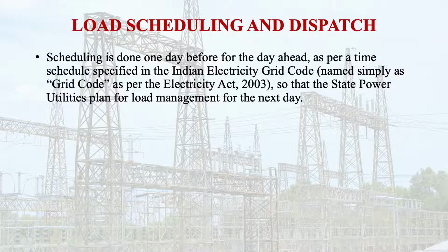Load schedules are prepared on a 15 minute basis. That means the load dispatch center prepares the schedule, or gets the schedule from the states or from the generating plants. It is scheduled on a 15 minute basis to see that the average generation of electrical energy over 15 minutes matches the load over those 15 minutes. The scheduling is done one day before, for the day ahead, as per a time schedule specified by the Indian Electricity Grid Code, which we know is under the Electricity Act 2003, so that the state power utilities plan the load management for the next day. So it is clear that it is done one day ahead.